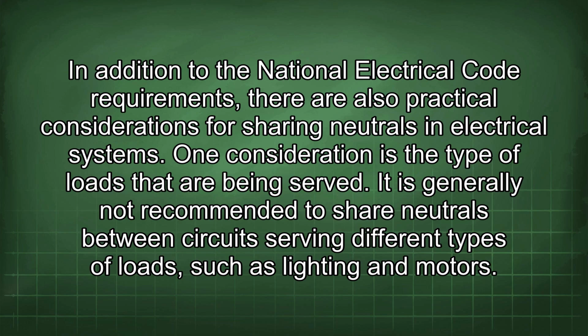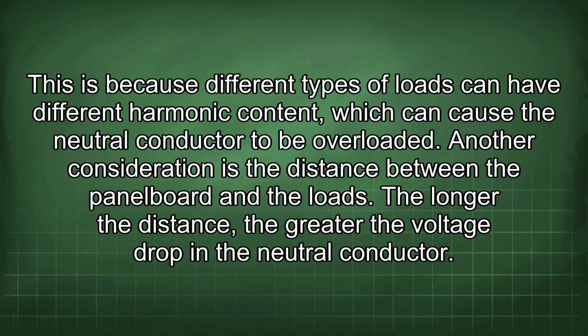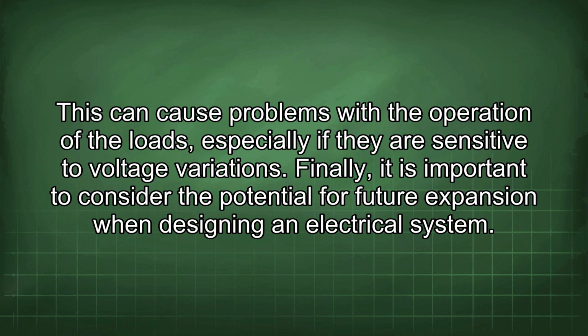systems. One consideration is the type of loads that are being served. It is generally not recommended to share neutrals between circuits serving different types of loads, such as lighting and motors. This is because different types of loads can have different harmonic content, which can cause the neutral conductor to be overloaded. Another consideration is the distance between the panel board and the loads. The longer the distance, the greater the voltage drop in the neutral conductor. This can cause problems with the operation of the loads, especially if they are sensitive to voltage variations.